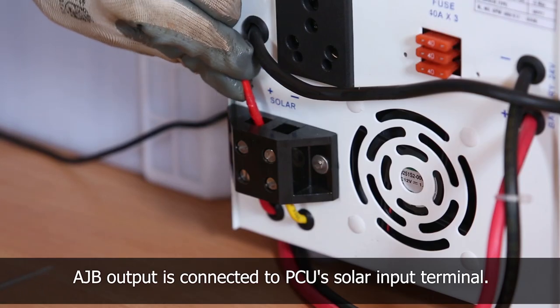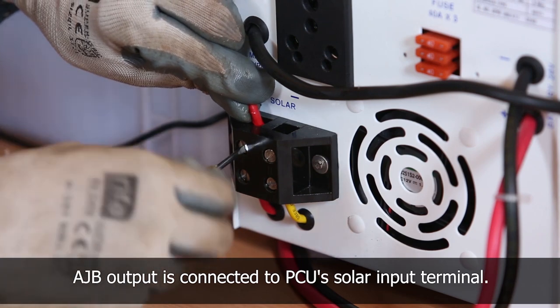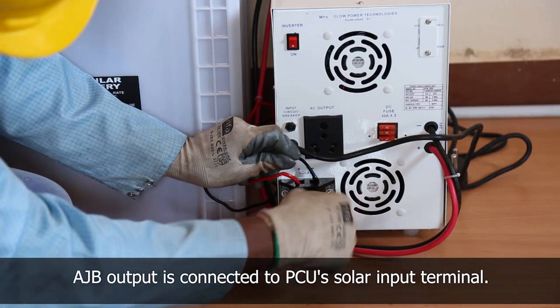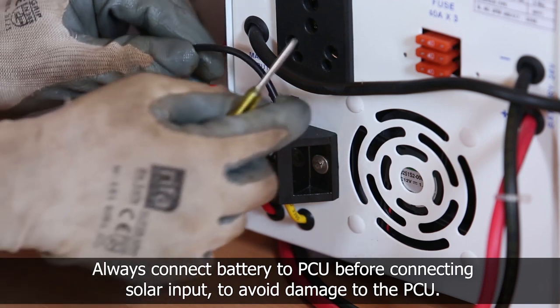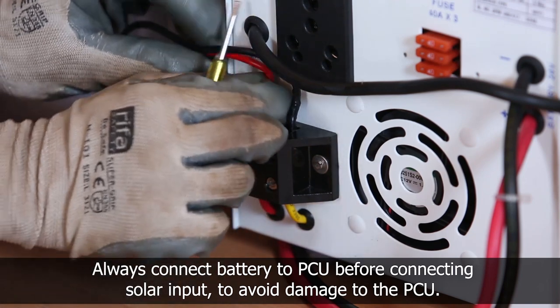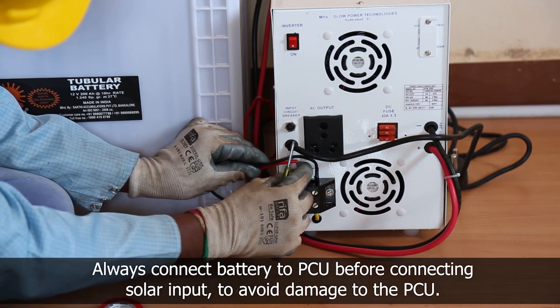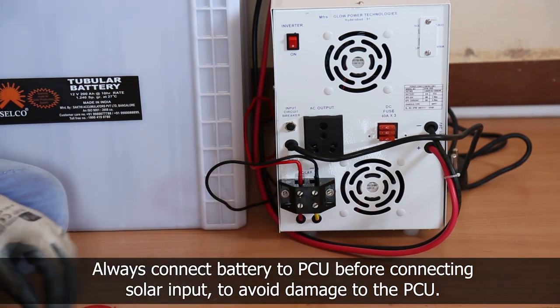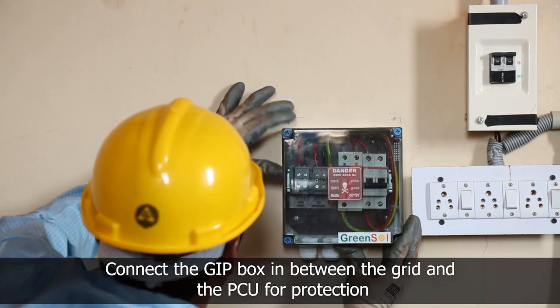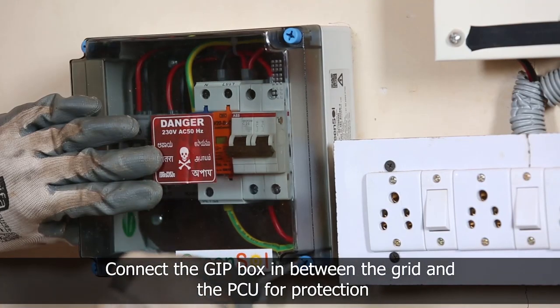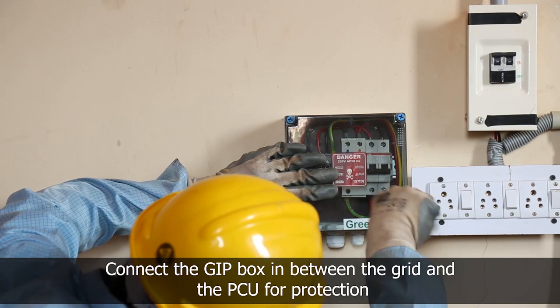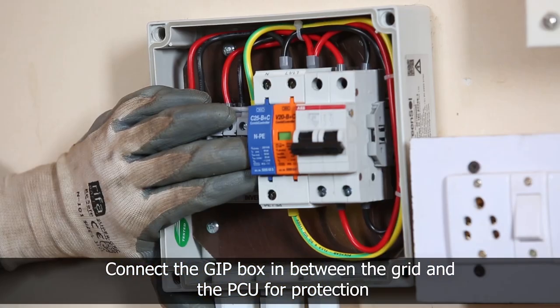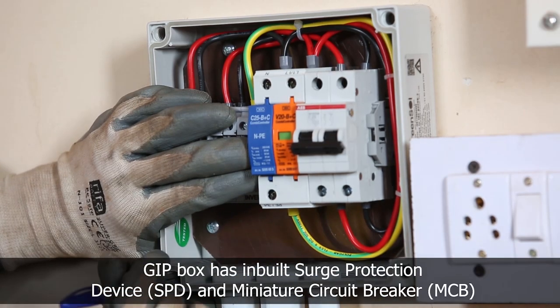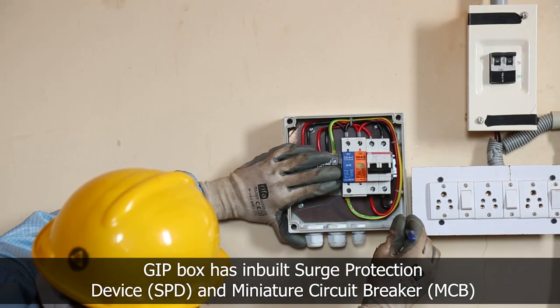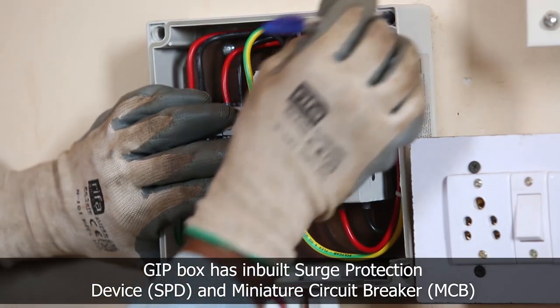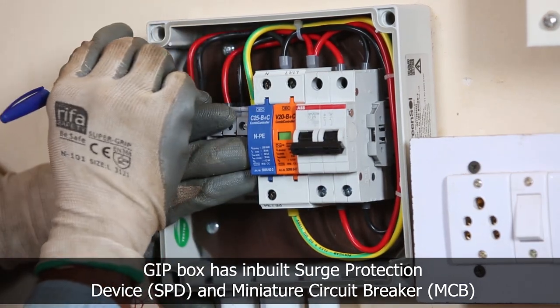Now, connect the array junction box output to the power conditioning unit's solar input terminal. Always connect the battery to the power conditioning unit before connecting the solar input to avoid any damage to the power conditioning unit. After that, connect the grid input protection box in between the grid and power conditioning unit for protection. Grid input protection box has an inbuilt surge protection device and a miniature circuit breaker for protection against voltage and current fluctuations.